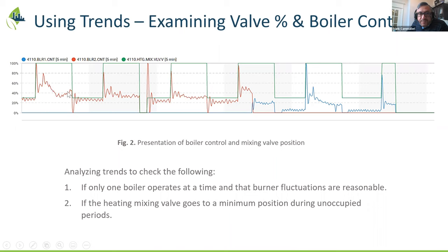This is good. The other thing we're looking for is whether the heating mixing valve goes to a minimum position during unoccupied periods. That's this piece here - the valve position with this green line, during unoccupied periods, is actually going to 30% in this case.